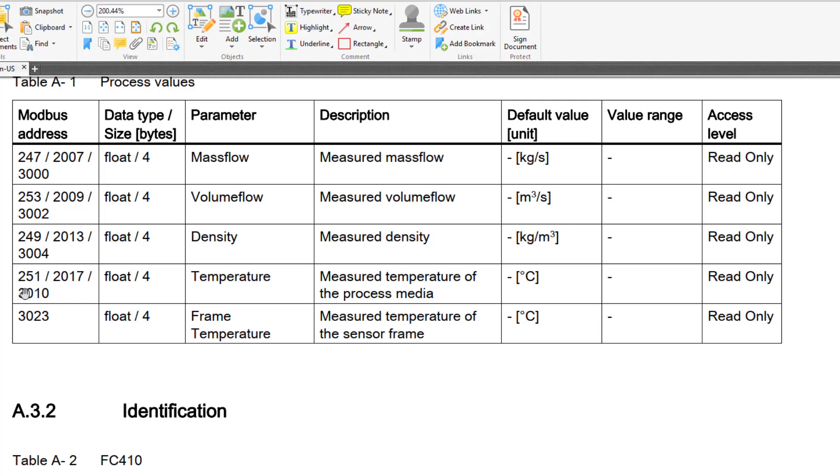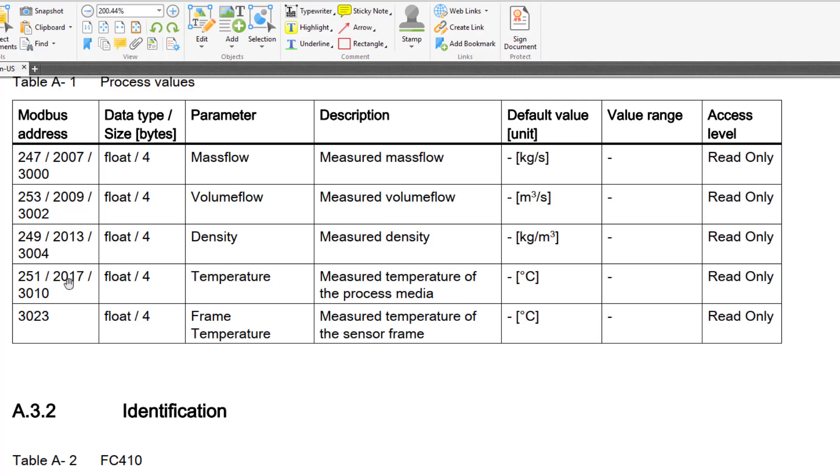Now what you can't do is read blank locations. So you can see here 3004 but there is nothing at 3006 and 3008. You can't just make that up and say I am just going to add another 6 on to get me up to this temperature value and ignore the other 2 memory locations. Because there is physically nothing there you will get a bad response back and that read won't work within TIA Portal. So you would have to do a separate read for the temperature.